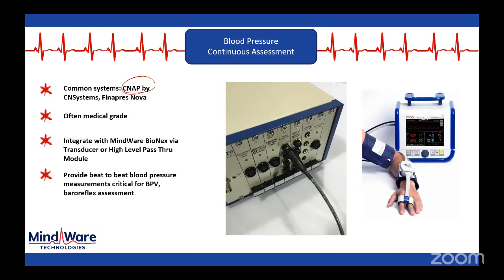Most commonly, we find people are using one of two devices to do this. There's the CNAP, which is sort of our preferred device for this, and that's by a company called CN Systems. And then there's the Finapres Nova. Both operate using this dual approach where there's a cuff on the arm that is taking baseline measurements over time. And then there are additional cuffs, either on the wrist or the fingers, that are maintaining more constant pressure assessments at those extremities. And that's the way in which we're able to get this continuous representation of blood pressure over time. So you can see cycle by cycle, beat by beat, what the diastolic and systolic blood pressures are for that given beat.